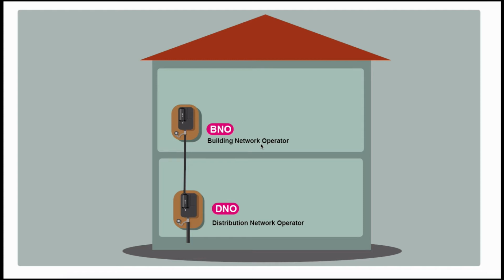That all sounds very grand, and you can imagine that's the case in a big office or some factory or something like that. But this is just your standard two flat house, you haven't got a building network operator. You just want your service dealing with, but they won't do that. So quite often what you have to do is run a whole new supply in from the street, because the DNO will not work on this, and you can't work on this because you've got to isolate this section. So that can often cause problems.